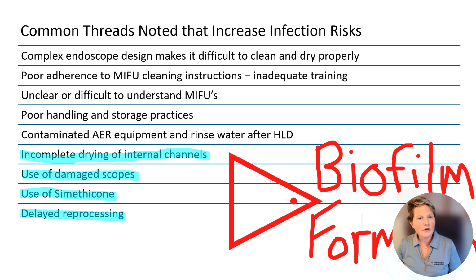Here are some common threads that are noted that increase infection risks. First, complex endoscope design, which we talked about a little bit, making it difficult to properly clean and dry properly. And then poor adherence to the manufacturer's instructions for use as far as the cleaning instructions go, and maybe not as good of training as there could be. Unclear or difficult to understand manufacturer's instructions for use. Sometimes they require extra clarity. And then poor handling and storage practices. Sometimes people are not wearing gloves when they're handling the scopes, which is kind of endoscope 101 handling for me. You absolutely should be wearing gloves after performing hand hygiene every time you're handling a scope.